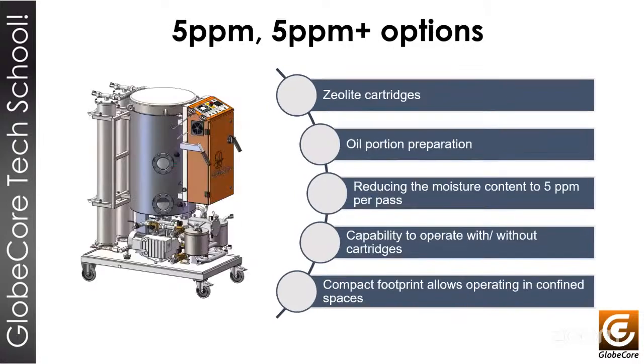Also, we will talk about the 5 ppm and 5 ppm plus options. Another improvement of our equipment is the newly developed 5 ppm and 5 ppm plus options. The main objective of the development of this equipment was to achieve a low oil moisture content in a single pass of the oil portion through the machine. That means we will take a portion of oil in this machine. The oil will go into the machine, and this oil will not leave the machine if we don't reach 5 or less ppm of moisture inside of the oil, in a single pass.